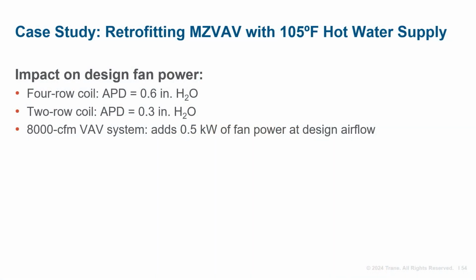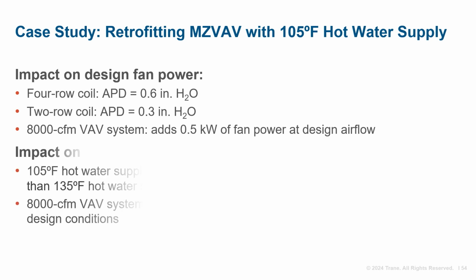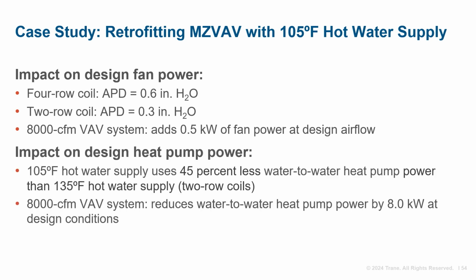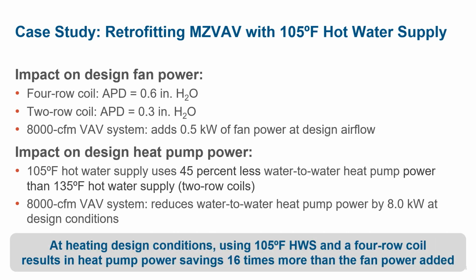For this VAV system, when supplying 100% design airflow during morning warm-up, the VAV box with a 4-row coil adds 0.5 kilowatts to the fan power. But if 2-row coils were used, 135-degree hot water would be needed. Operating the water-to-water heat pump at 105 degrees rather than 135 degrees reduces the heat pump power by 8 kilowatts. So 105 degrees and 4-row coils save 16 times more heat pump power than it adds in fan power.